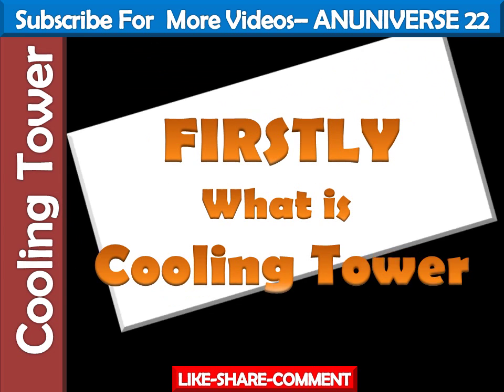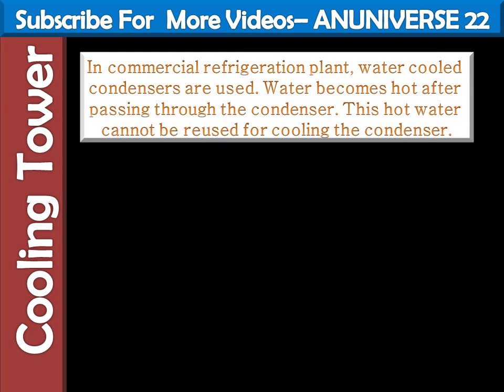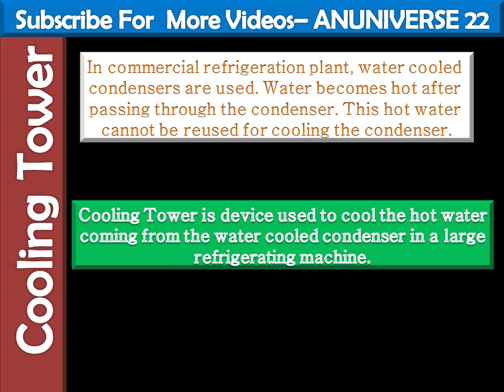What is the cooling tower? A cooling tower is an enclosed tower-like structure through which atmospheric air circulates to cool large quantities of water by direct contact. In commercial refrigeration plants, water-cooled condensers are used. Water becomes hot after passing through the condenser and this hot water cannot be reused for cooling the condenser. So, a cooling tower is a device used to cool the hot water coming from the water-cooled condenser in a large refrigerating machine.